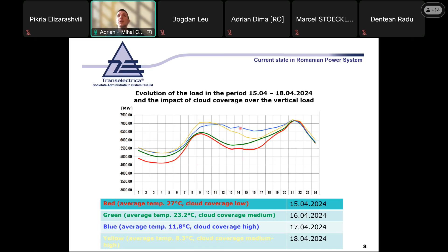Looking just two days later, the cloud coverage was really high, meaning there was no PV infeed from the prosumers, and the average temperature was lower. You can see a huge difference of load between the two curves, up to 1,300 megawatts, which is what the prosumers were producing on the 15th of April. On the other day, there was no prosumer production, so the whole load of the prosumers was taken by the grid, increasing the vertical load.